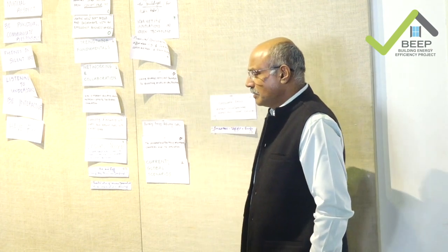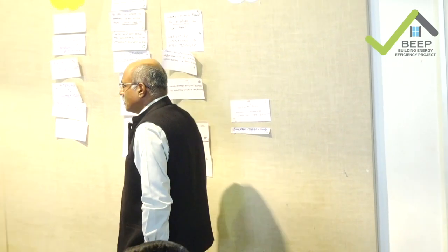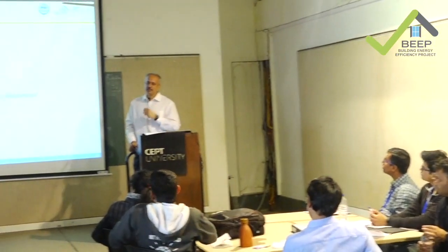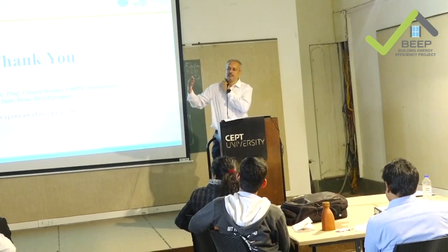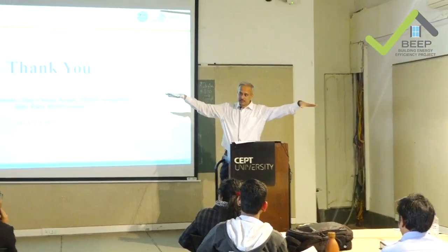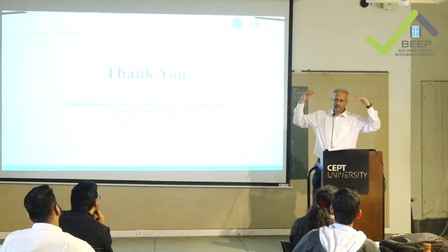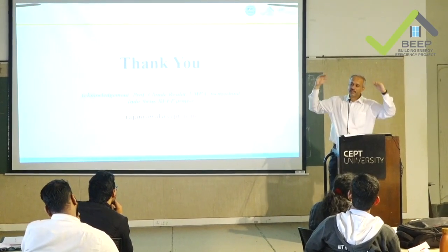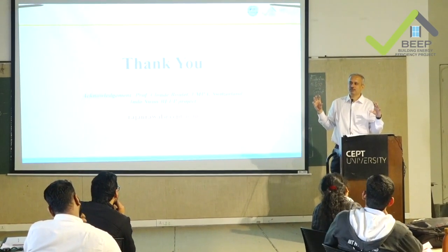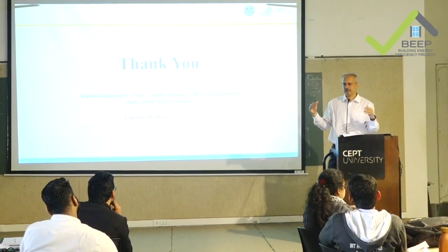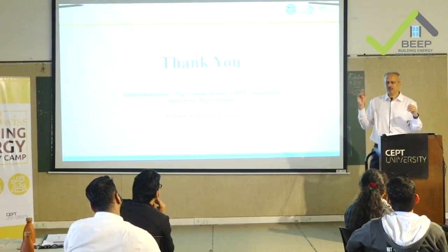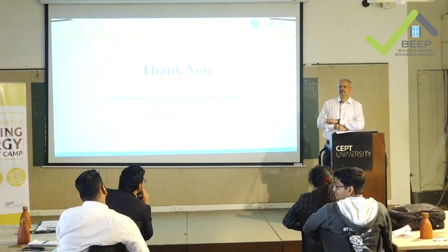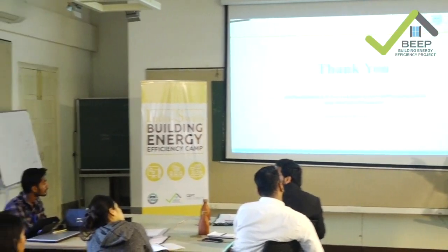So SRI increases the UHI effect or? So higher SRI reduces the urban heat island effect. That means of the amount of radiation you are receiving on the total mass, 2 things happen. You are reflecting right away, and high emittance also helps you to reject whatever you are gaining. So it reduces the heat island effect. Do you know what heat island effect is? Okay. Yes. It's related to that.